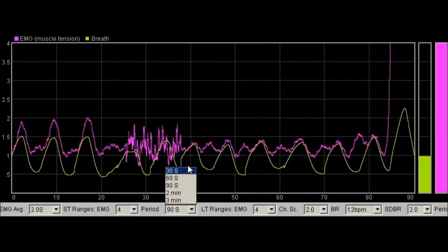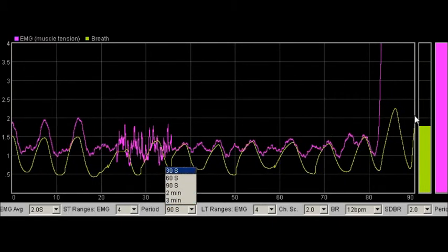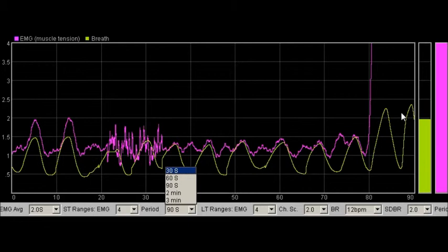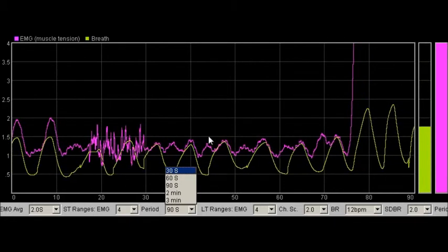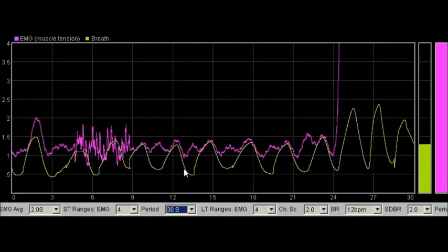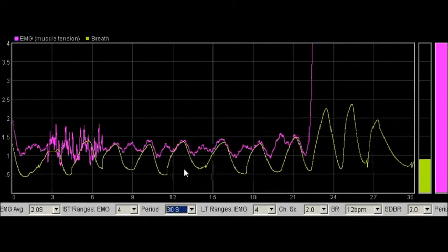The fourth control sets the length of time it takes for the traces to traverse the whole chart from right to left, or in other words the horizontal range. You can see that if I set it to something lower, the traces go faster.